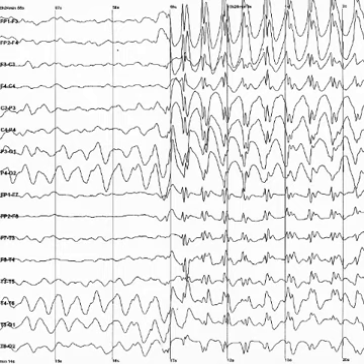Simultaneous EEG recordings and FMRI scans have been obtained successfully, though successful simultaneous recording requires that several technical difficulties be overcome, such as the presence of ballistocardiographic artifact, MRI pulse artifact and the induction of electrical currents in EEG wires that move within the strong magnetic fields of the MRI. While challenging, these have been successfully overcome in a number of studies. MRIs produce detailed images created by generating strong magnetic fields that may induce potentially harmful displacement force and torque. These fields produce potentially harmful radio frequency heating and create image artifacts rendering images useless.